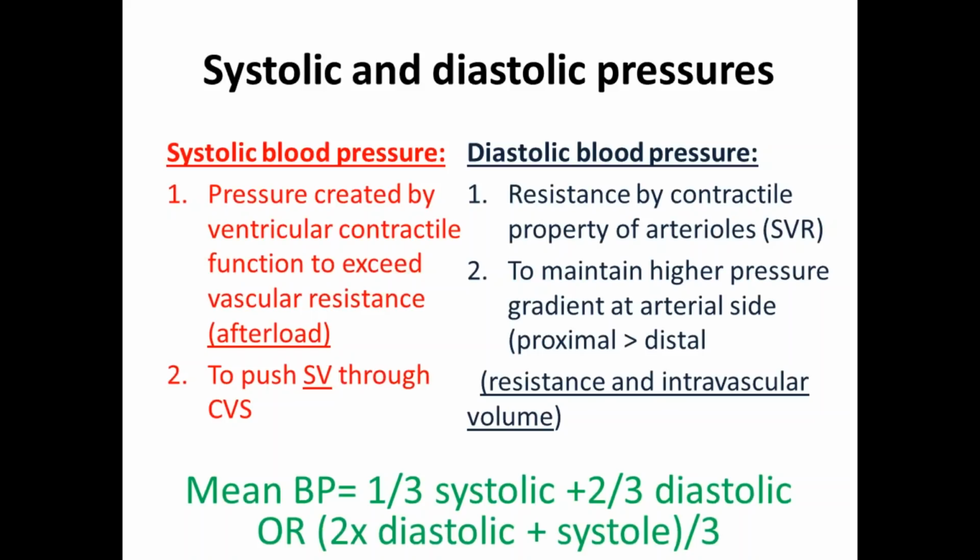It is the way that the monitor measures the blood pressure if you measure it indirectly. But direct blood pressure is different. It is the mean area below the curve if the machine is measuring direct blood pressure. So if the machine is measuring invasively, it is a different way to calculate the mean, different from the Dinamap or the indirect way of blood pressure measurement.